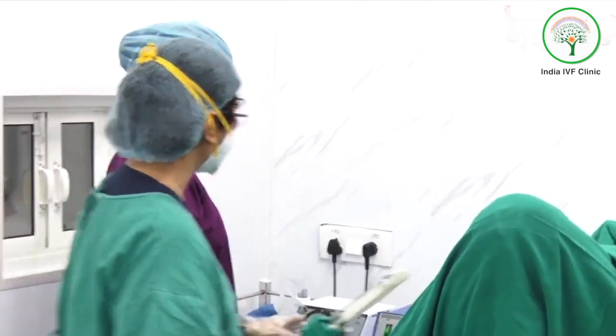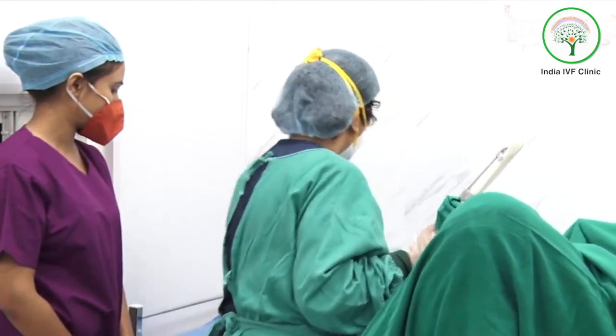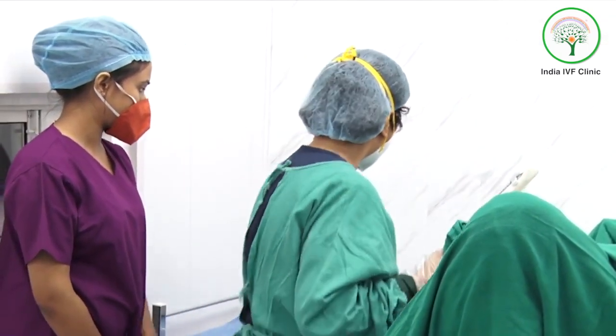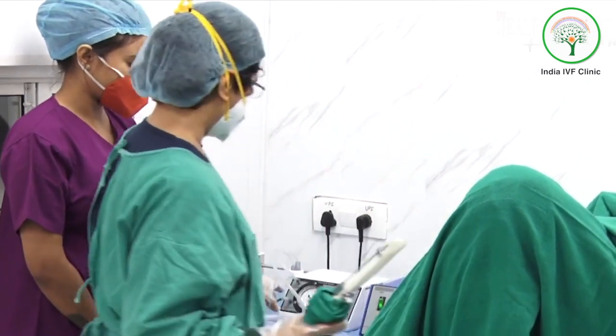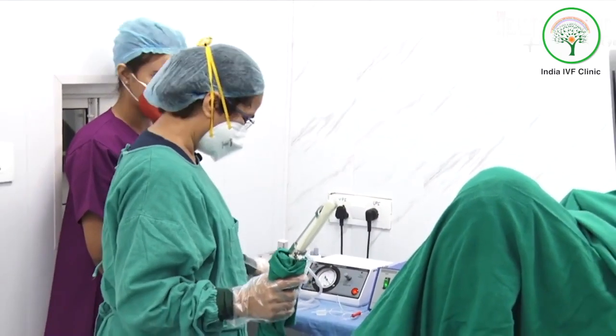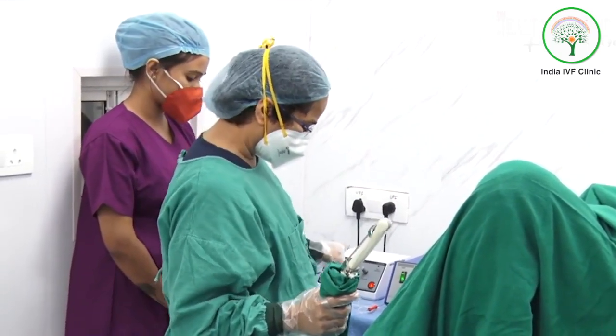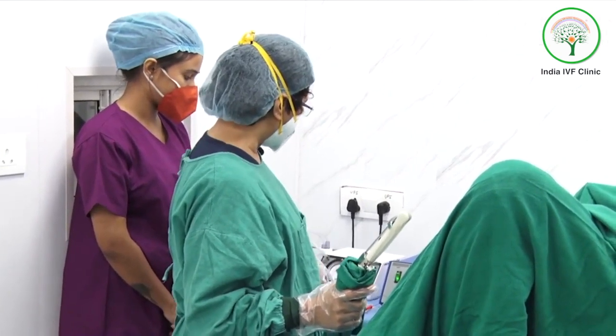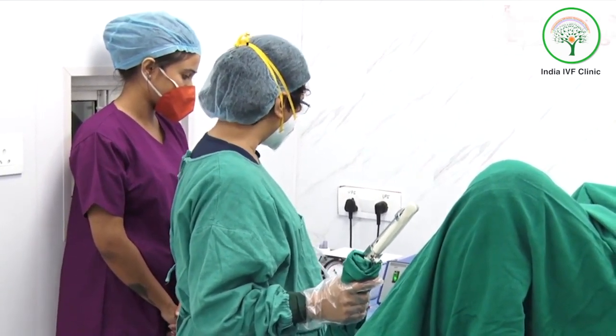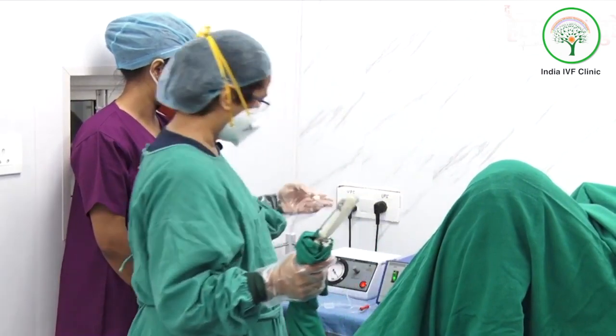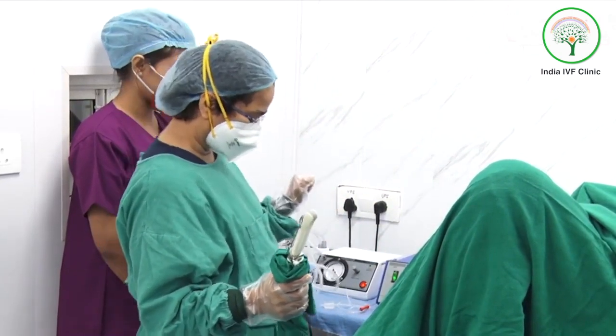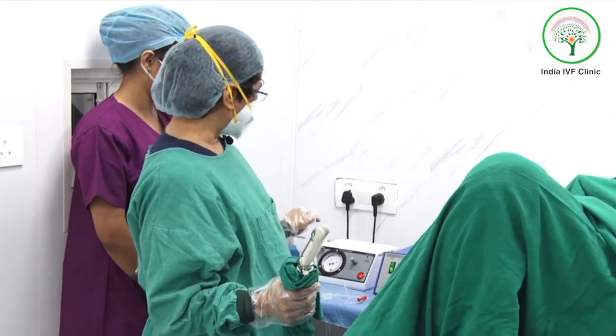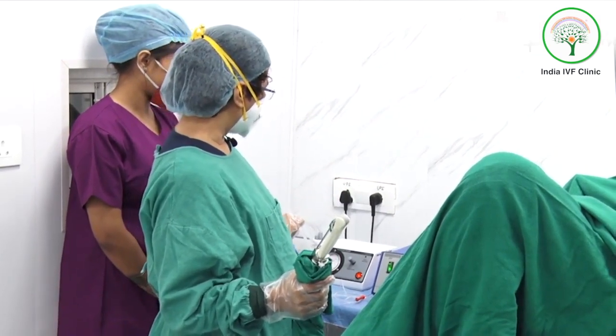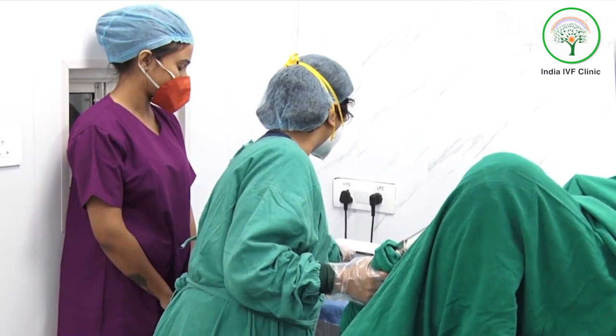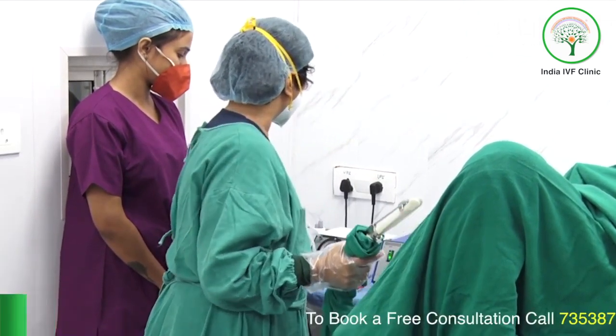Now we have to see that all the machines are ready. Basically this is a suction pump from which we aspirate. You have to check before performing whether it is working properly or not. You press the button and check that everything is fine. To check it, you have to close this end, because then a pressure will be maintained. You see the pressure is going up to 300, 400, it is not good. So you have to reduce the pressure. Now it is coming to 200, it's fine.